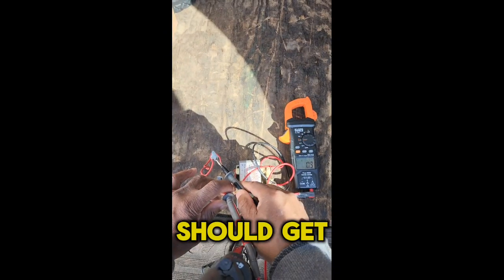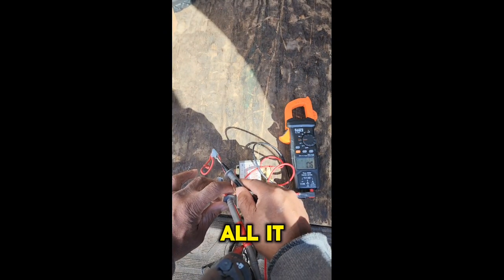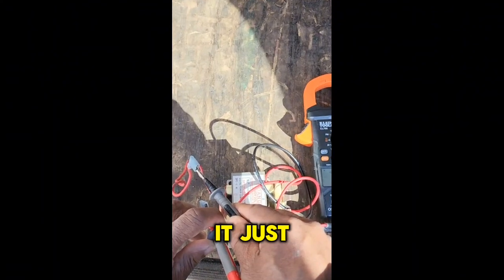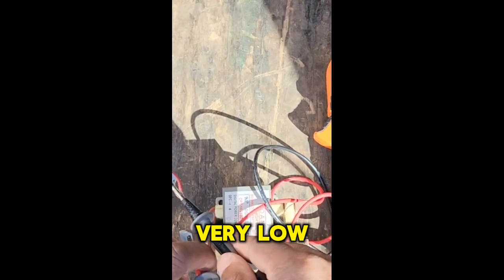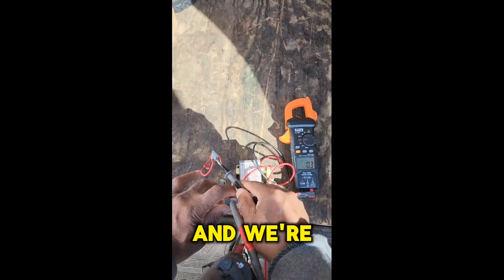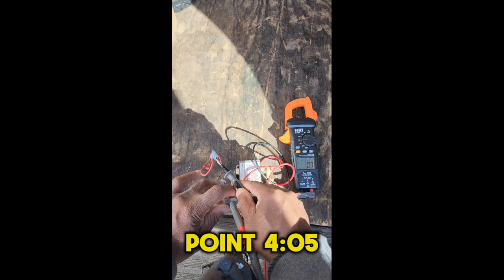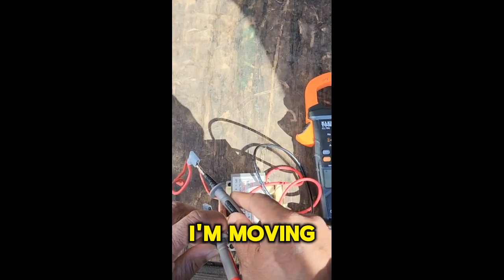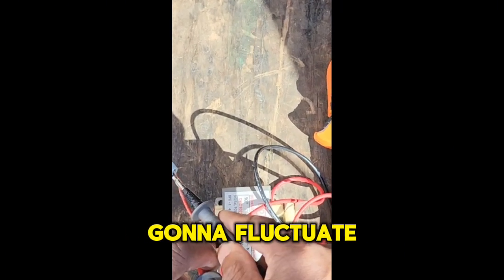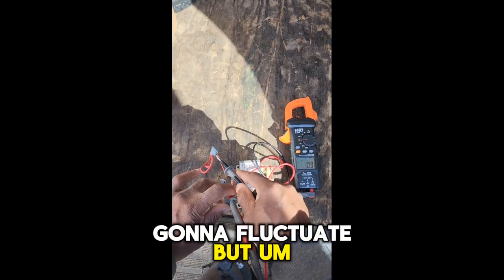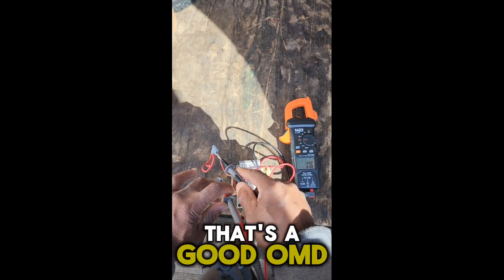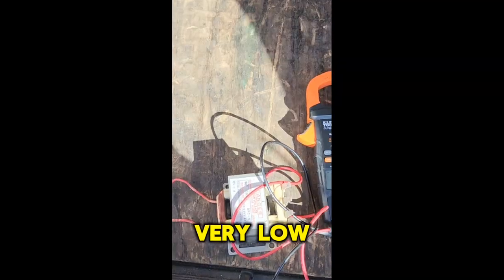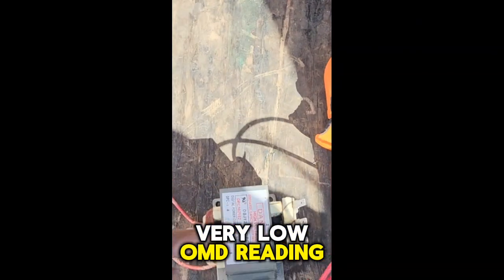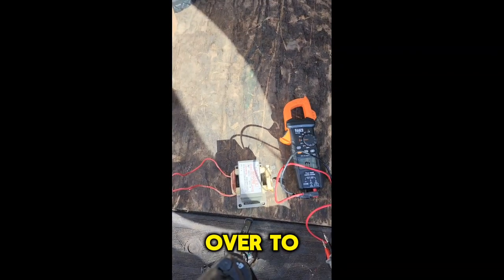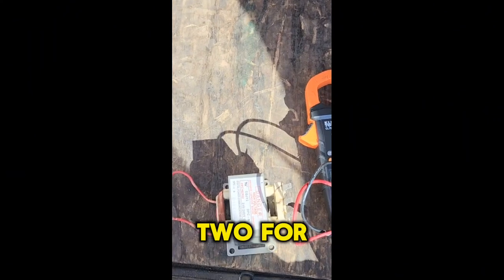So right there, all it asks for is, it just says that you should get a very low ohms reading, and we're getting 0.45. I'm moving around a little bit, so it's going to fluctuate, but that's what we're getting. That's a good ohms reading, a very low ohms reading. So now let's go over to number 1 and number 2.